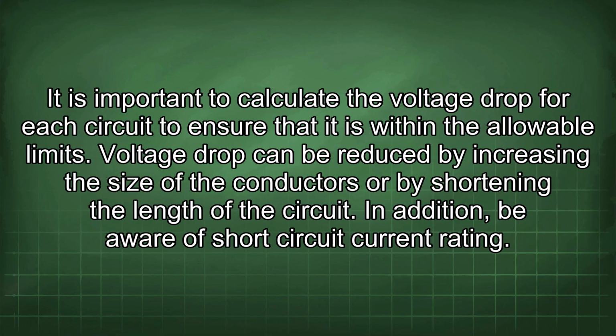It is important to calculate the voltage drop for each circuit to ensure that it is within the allowable limits. Voltage drop can be reduced by increasing the size of the conductors or by shortening the length of the circuit. In addition, be aware of short circuit current rating.